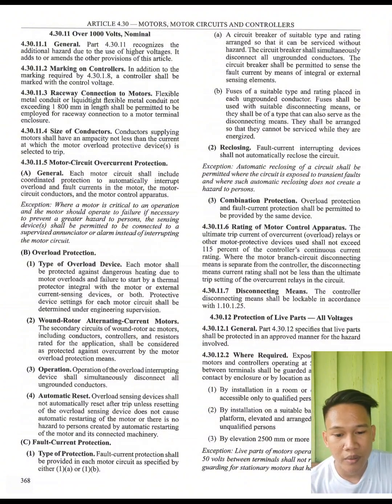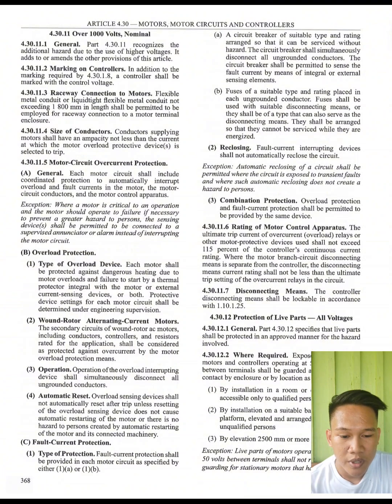Next is 4.30.11.5 Motor circuit overcurrent protection. A, General. Each motor circuit shall include coordinated protection to automatically interrupt overload and fault currents in the motor, the motor circuit conductors, and the motor control apparatus. Exception. Where a motor is critical to an operation and the motor should operate to failure if necessary to prevent a greater hazard to persons, the sensing device shall be permitted to be connected to a supervised annunciator or alarm instead of interrupting the motor circuit.